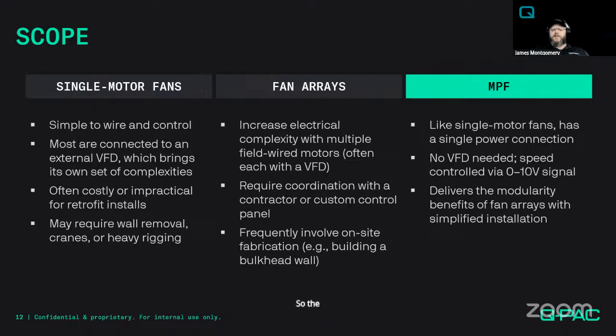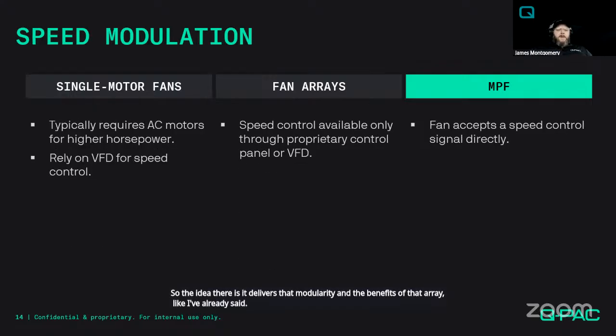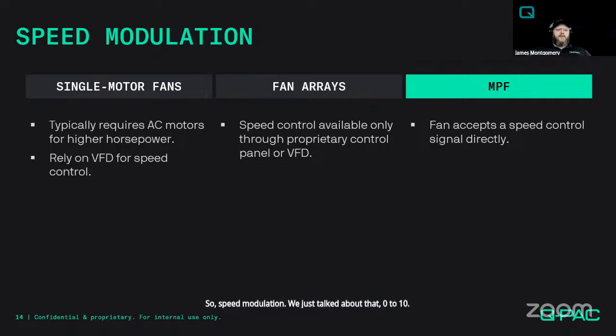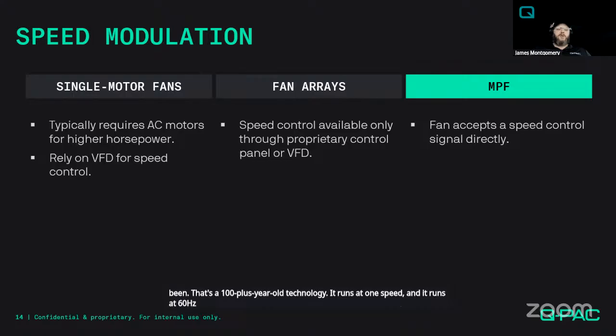So the idea there is it delivers that modularity and the benefits of that array, like I've already said. So speed modulation, we just talked about that, 0 to 10. Not to stick on this for too long, but single motor fans, AC motors, they're designed to run at a constant speed. And they always have been. That's a 100-plus-year-old technology. It runs at one speed, and it runs at 60 hertz, and that's all you get. Well, the addition of a VFD gave us the ability to control and turn down that speed. And that was a great feature that came along.